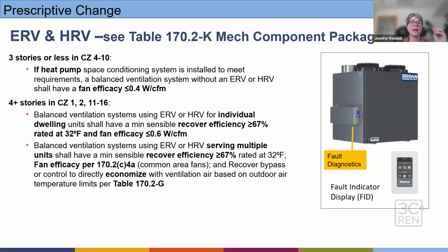There have been some updates now on the balanced ventilation. There's a whole section on DOAS, dedicated outside air systems. I'm going to just direct the mechanical engineers to that.